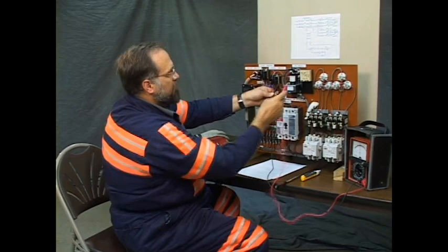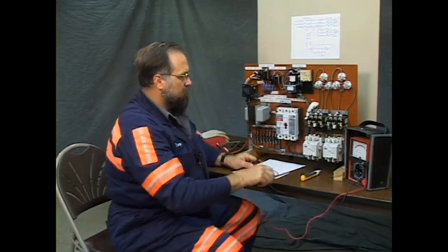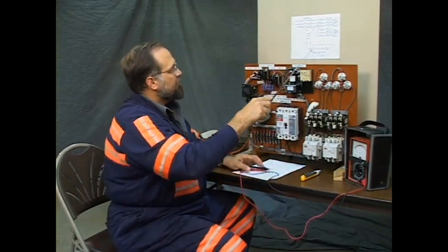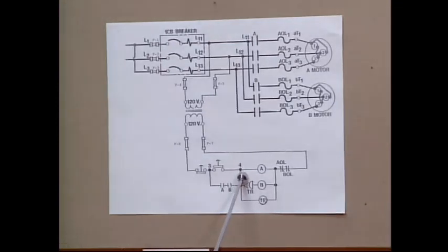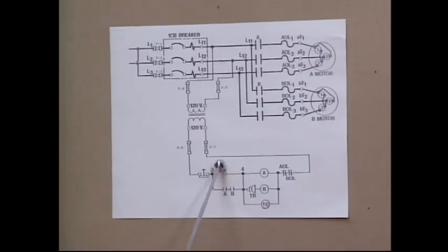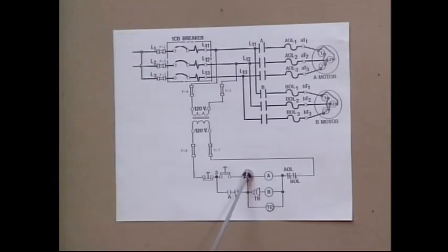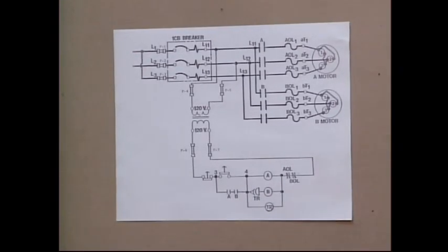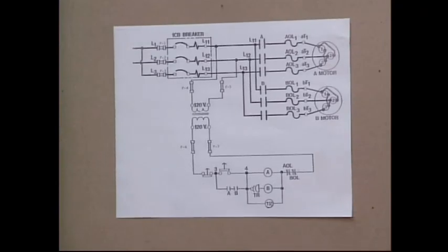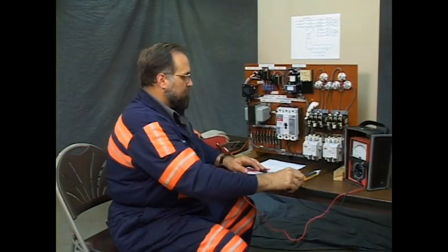And I do. So, those readings indicate that from the start switch to TR mercury tube, from the start switch to TR coil, read as they should. But from this point 4 to A is open, doesn't read. I believe that's our problem.